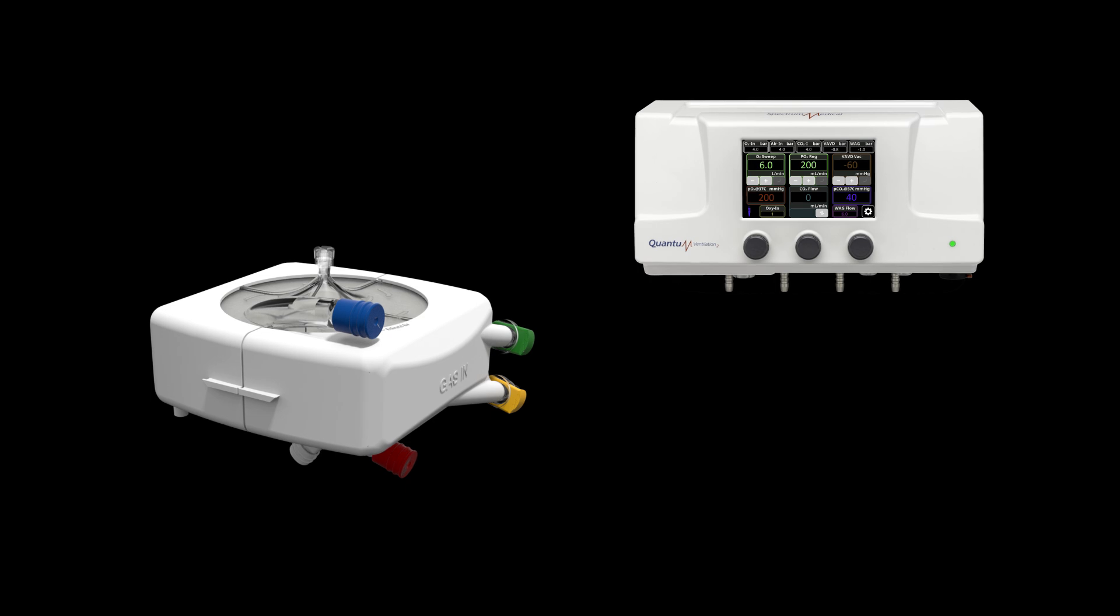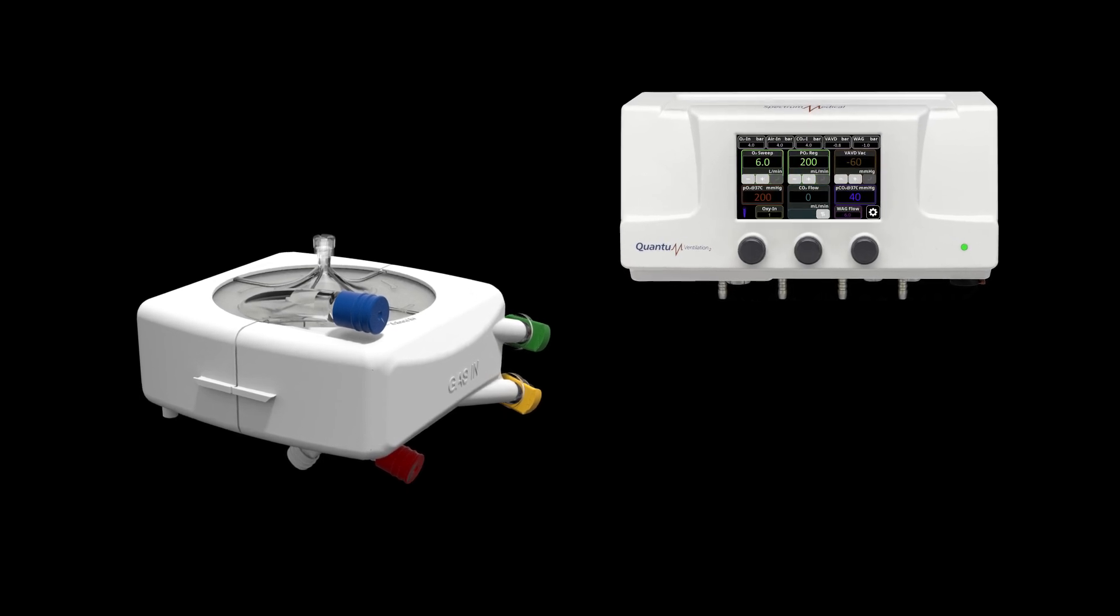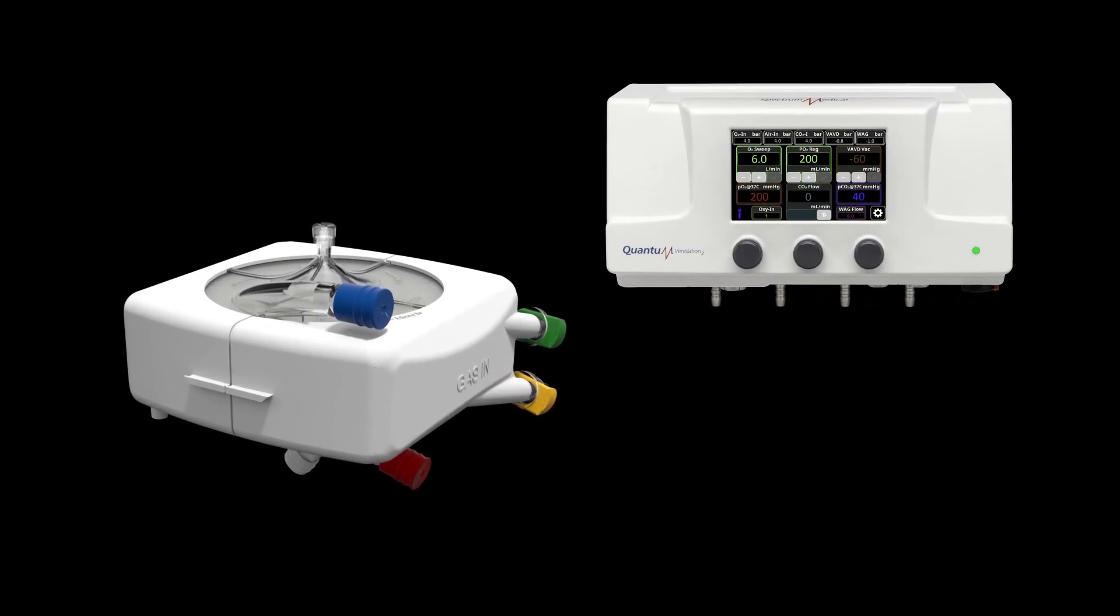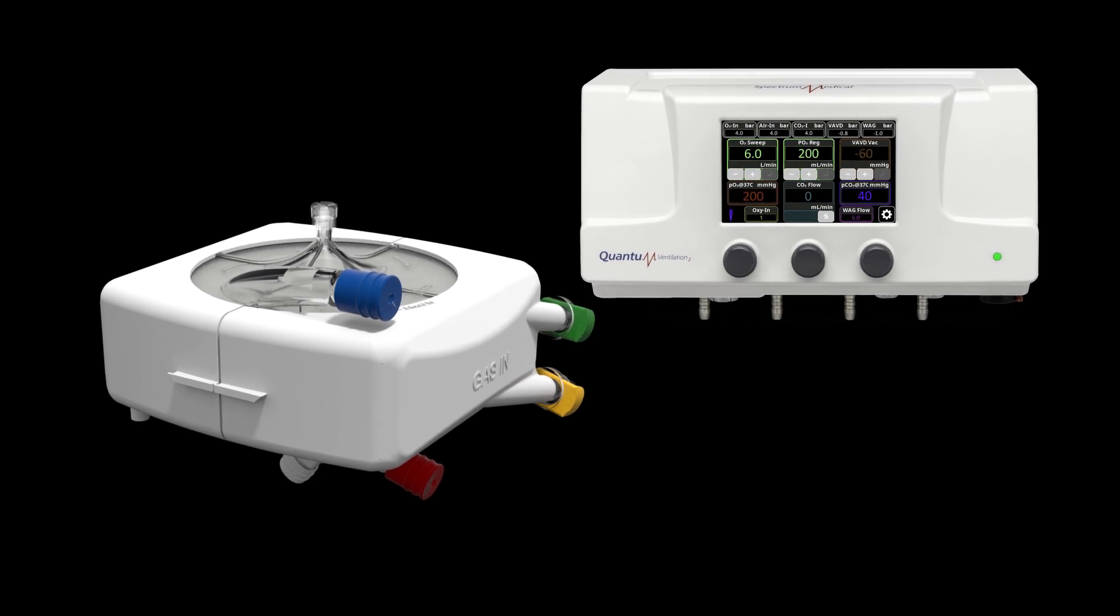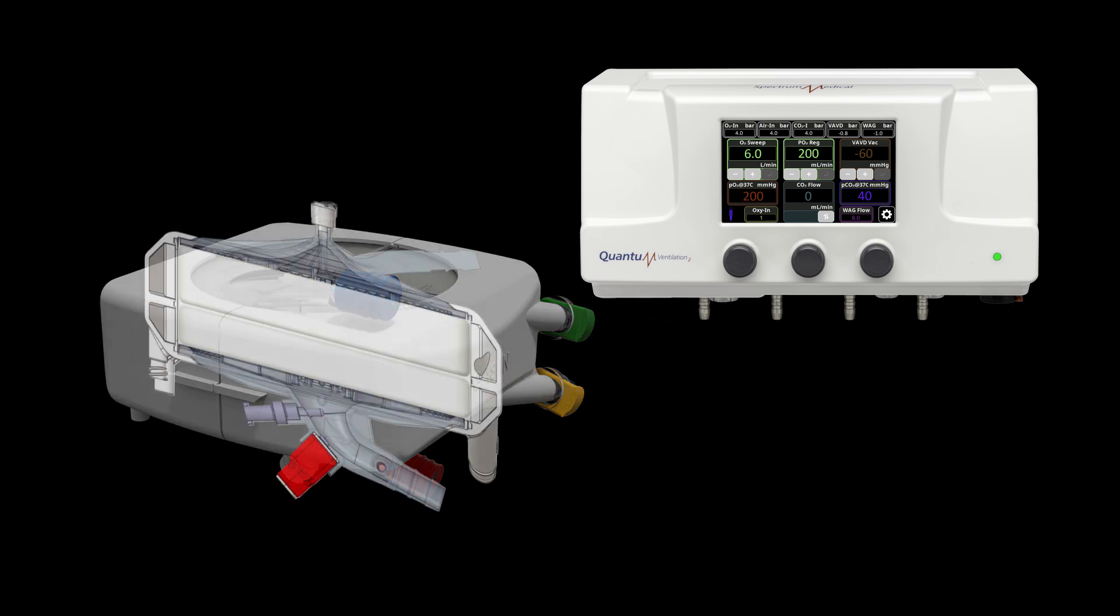Spectrum Medical's ventilation technology and dual chamber oxygenator are specifically designed to eliminate nitrogen in the sweep gas while also limiting oxygen pressure in the blood. Creating a VQ mismatch by passing blood through the oxygenator while limiting the total surface area of ventilated fibers. The resultant PaO2 is much lower than if all the fibers were ventilated.